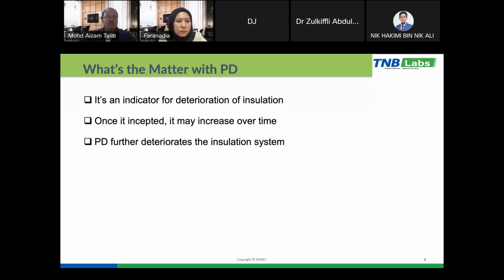But once the PD has occurred, or has been incepted, it may increase over time. We cannot stop it, but we can slow it down, but it still increases over time. And then it will further degrade or deteriorate the overall insulation system, and eventually the insulation system will fail, and it will fail the entire equipment. So it is important that we test, monitor, and analyze the presence of the PD, so that we can avoid the failure of the electrical equipment.